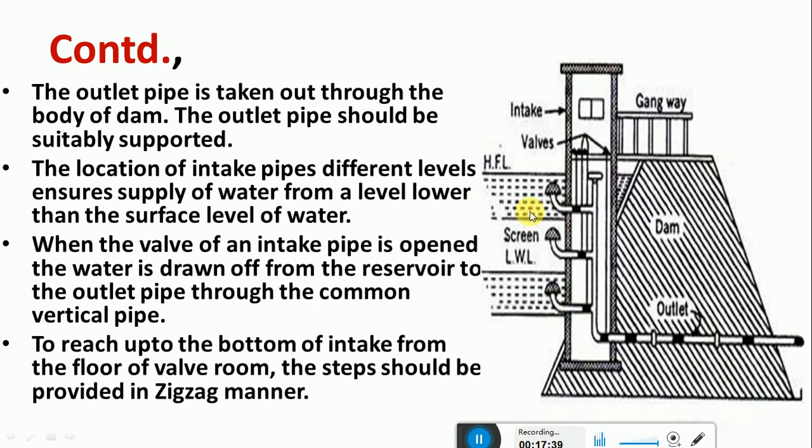Okay, so these are the valves which are placed at the top in a room. The access to this room will be provided through a gangway. A person can enter here for repair, maintenance and opening and closing of valves. Based on the level of the water, any one of the intake valves can be opened and the other 2 can be kept closed, and we can draw the water. If the water demand is more, then we can draw the water from all the 3 intake pipes. So this is the details about the reservoir intake.